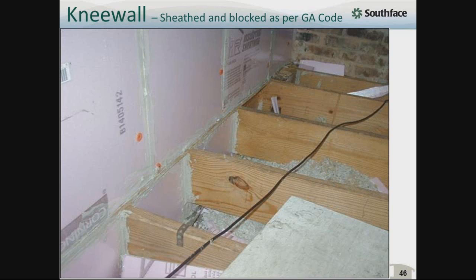One of the things with the blower door testing is, for the person who asked this, if they're looking for a way to demonstrate this to the builder you're working with, if you run the blower door and use a smoke stick while standing in the attic, if you're depressurizing the house, and if you move the smoke stick around the perimeter of the foam board, if you see smoke being drawn into that crack, that should do a good job of demonstrating to the builder that it's not actually sealed there. It is connected to the inside of the house.